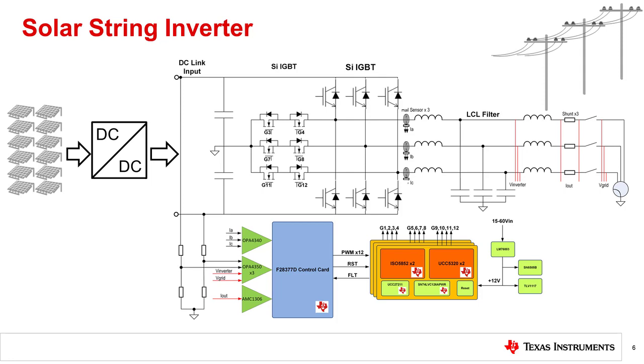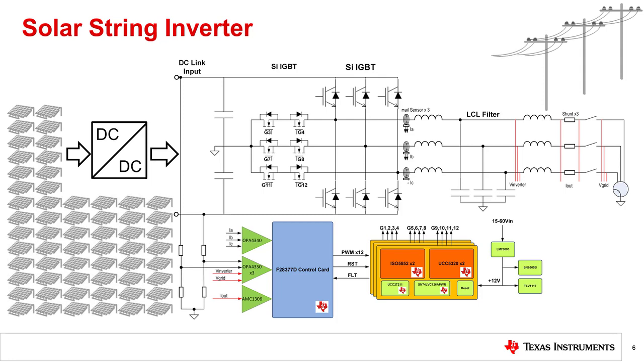Industrial-scale solar string inverters combine the outputs of many panels, and are continually pushing for DC bus voltages well above 600 volts to minimize I²R losses and to increase panel stack voltages. 800 volts or 1,000 volts are common levels today in 2018, with 1,500 volts expected in the near future. Non-isolated half-bridge drivers are not a suitable solution for the high-voltage buses of the future. For isolated gate drivers, 1,500-volt working voltage is available, with many existing solutions.